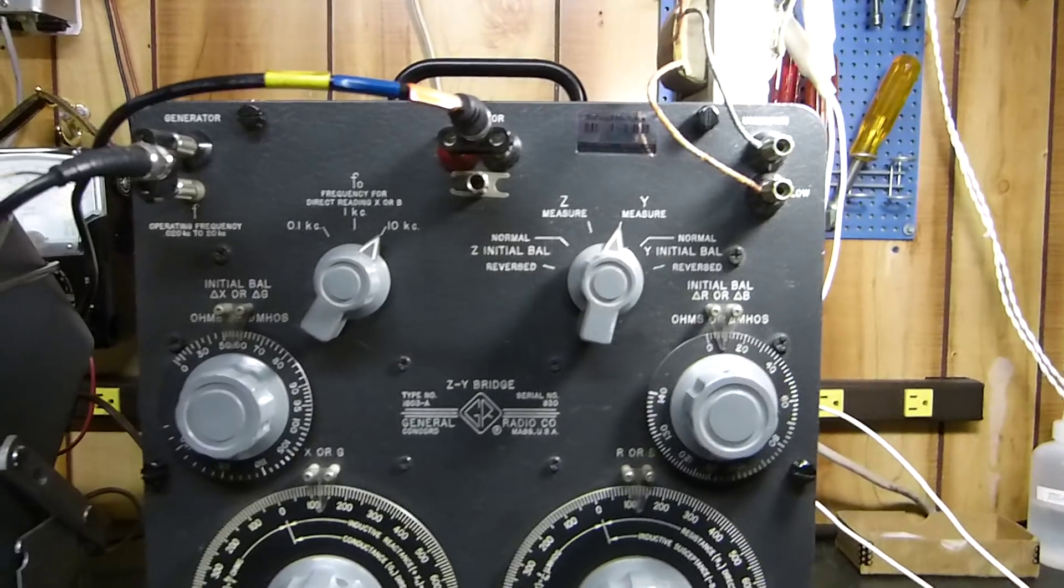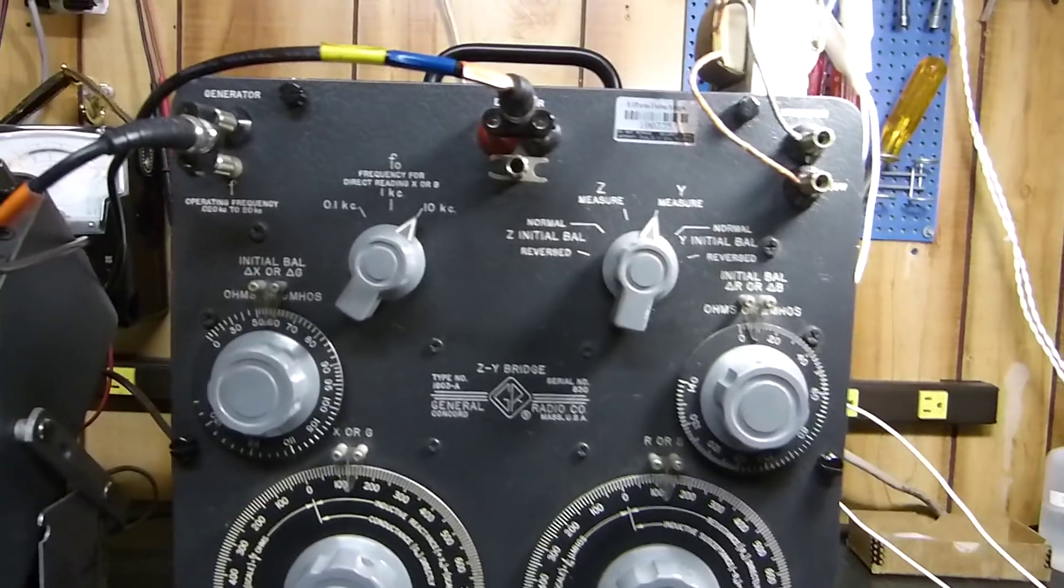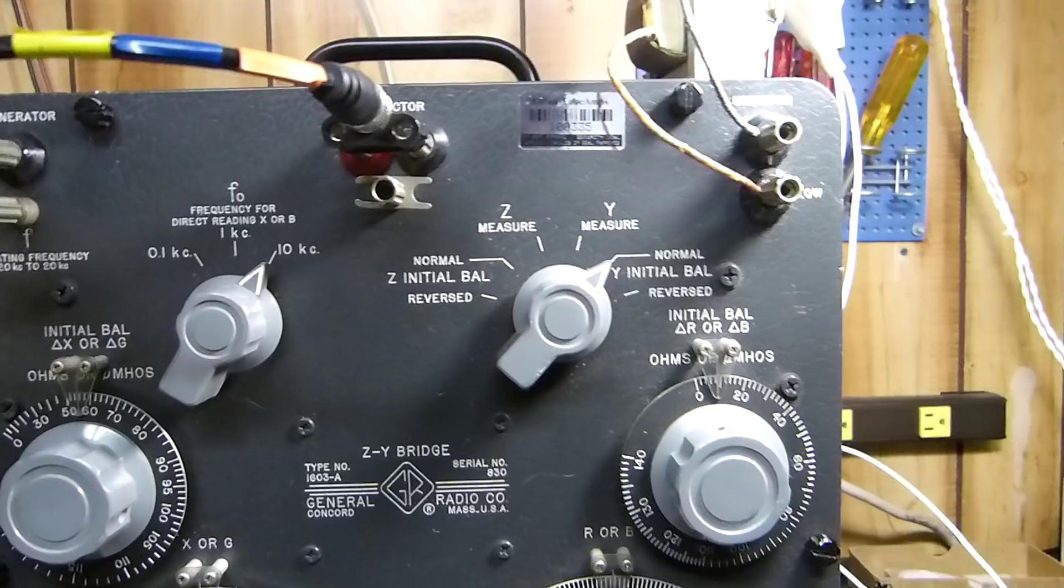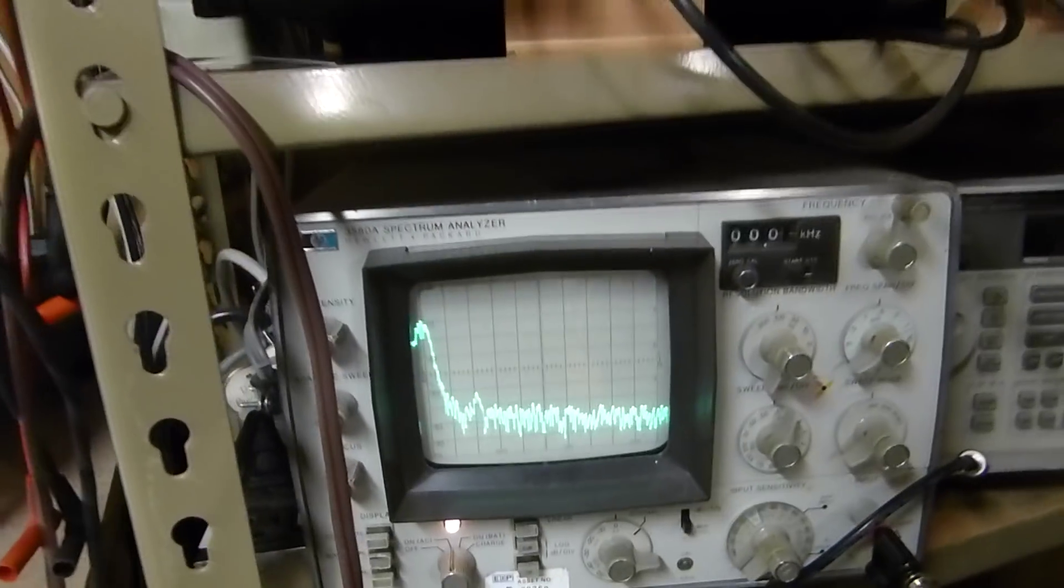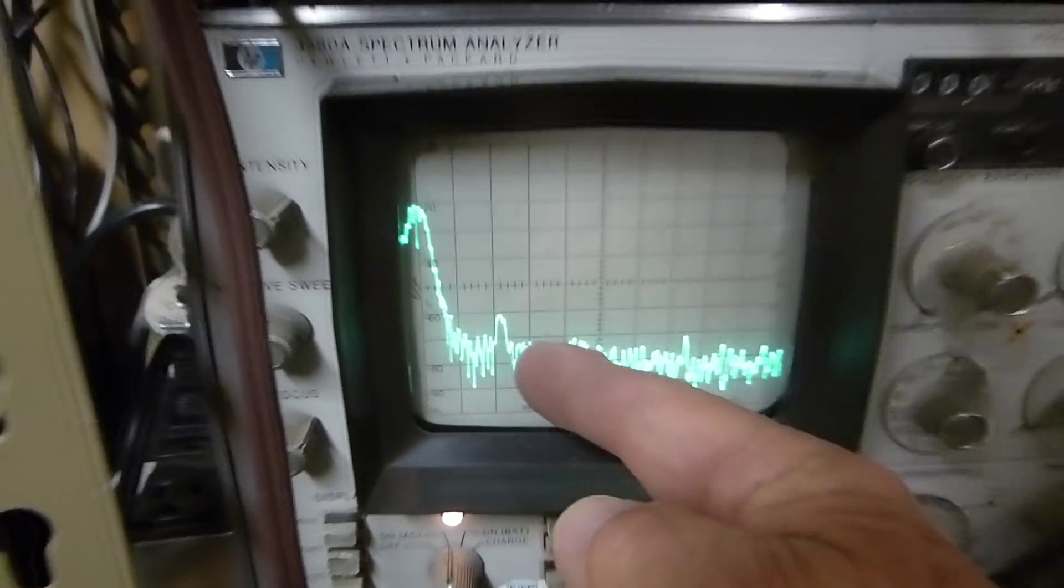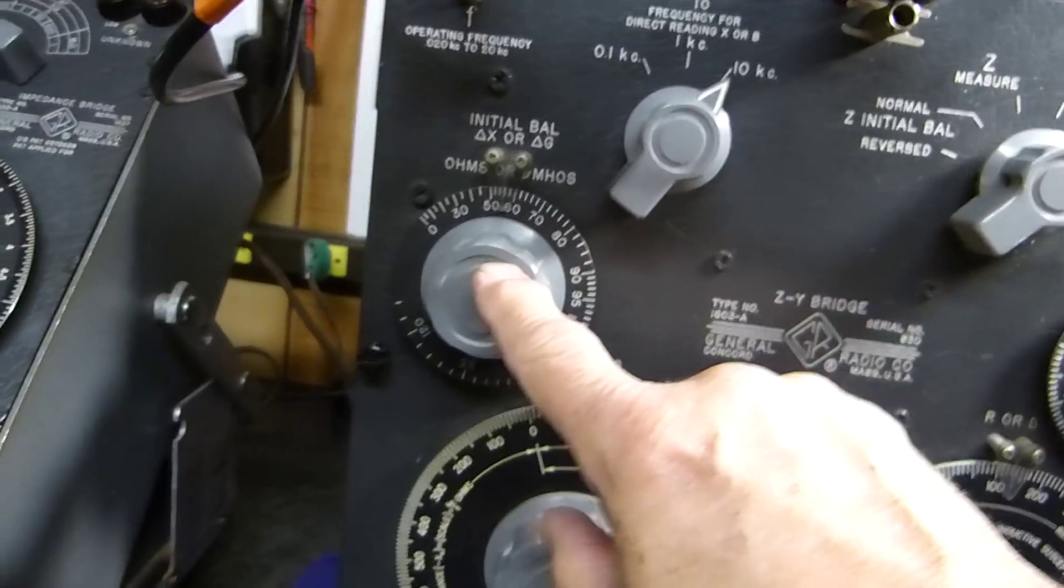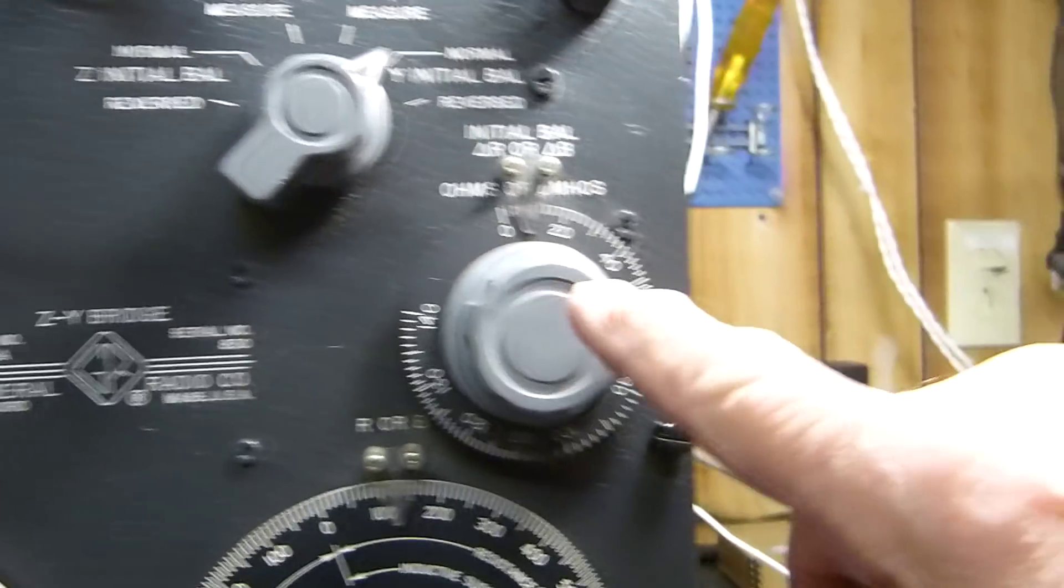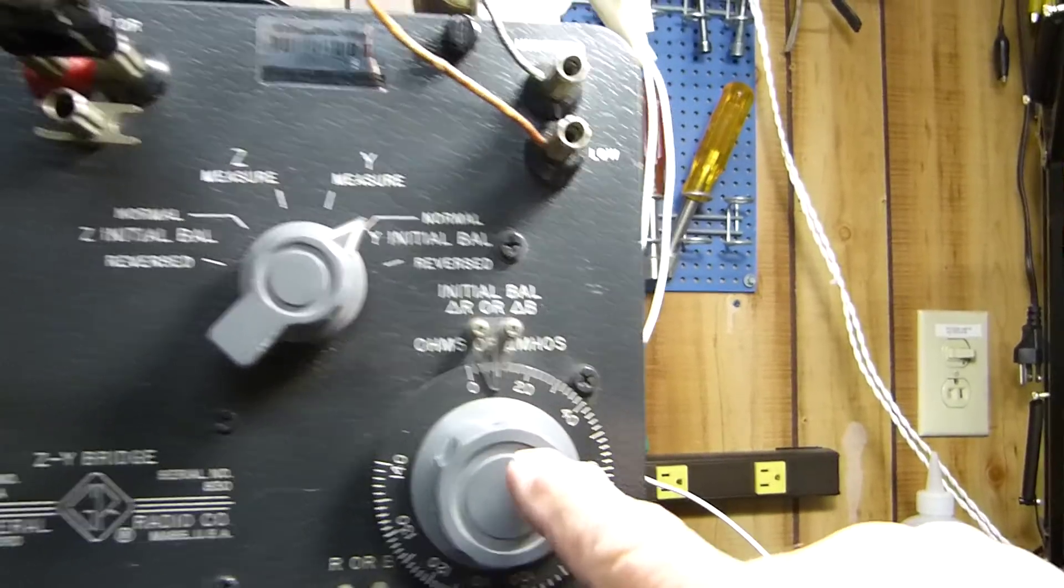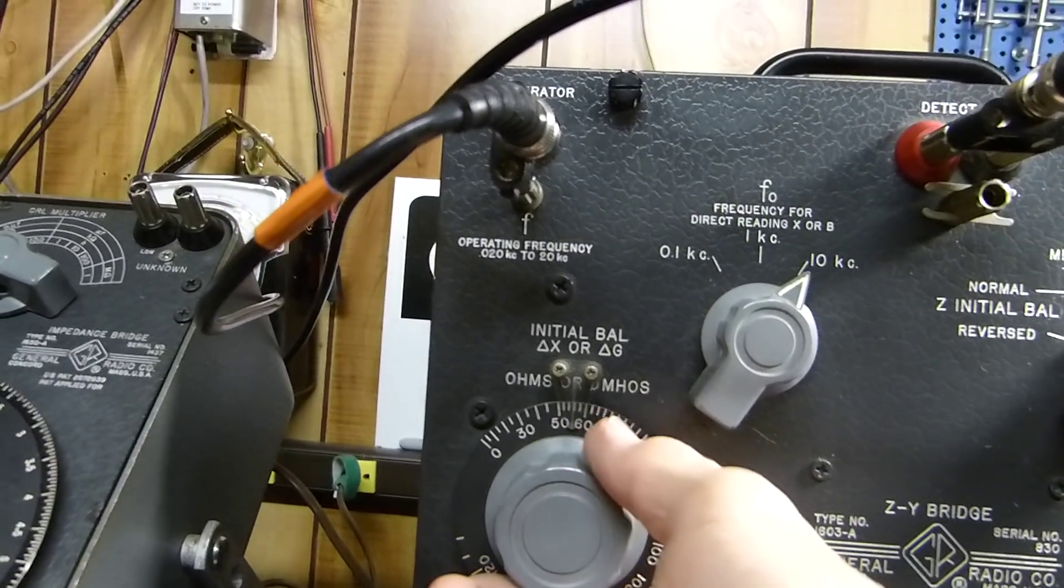It sounds complicated but it's really not that bad. It does take some tinkering. First, we balance it. We put it in Y initial balance and then we go over here and look at our spectrum analyzer. This is our pulse right here. I know it's tiny but it's because I've got it nulled. I'm going to throw it just a little bit out of null with these two knobs right here, the null knobs. This one measures ohms or micromhos, this one measures ohms or micromhos. Initial balance X or G, initial balance R or B.